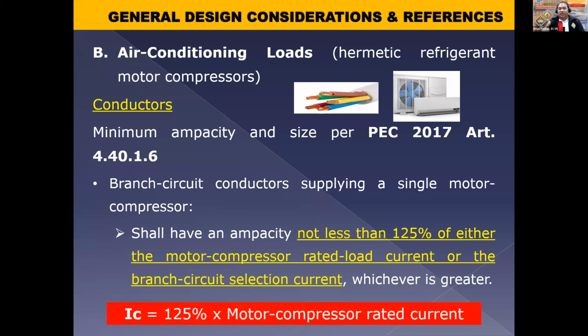Not the circuit breaker. Kasi for motor circuits, iba na yung function ni circuit breaker. Si circuit breaker now functions as a short circuit and ground fault protection, not for overload protection ng motors. Ang overload protection ng motors is handled by the overload relay, either solid state or yung thermal overload relays, no? Kaya nga ibang settings yung overload relay doon sa circuit breaker.